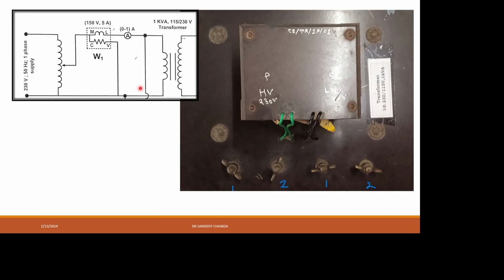After this we can see there is a transformer, and it has two windings, usually called primary or secondary, but in this particular transformer you won't find them labeled as primary or secondary. This transformer rating is 115/230 volt, 1 kVA. This side is called the LV side and this will be the HV side. So in a transformer you first have to find out the LV side and HV side, and both windings will have two ends, one the starting end and the other the end.